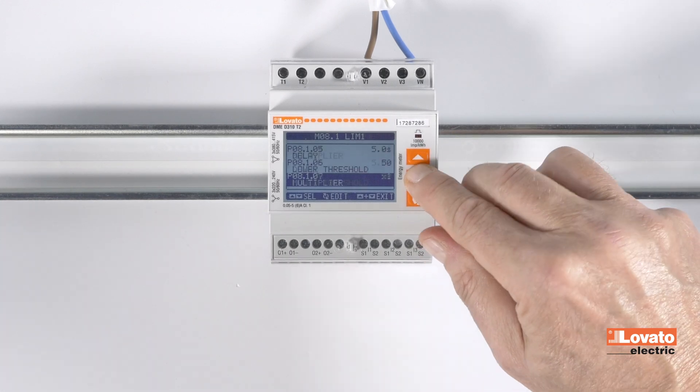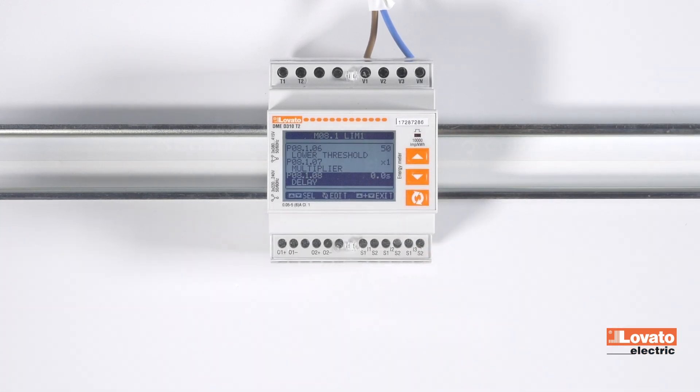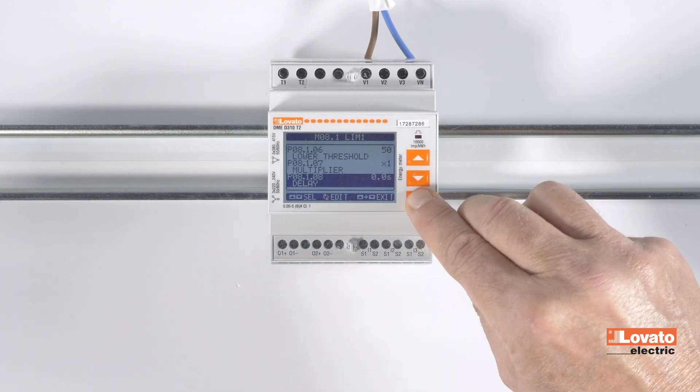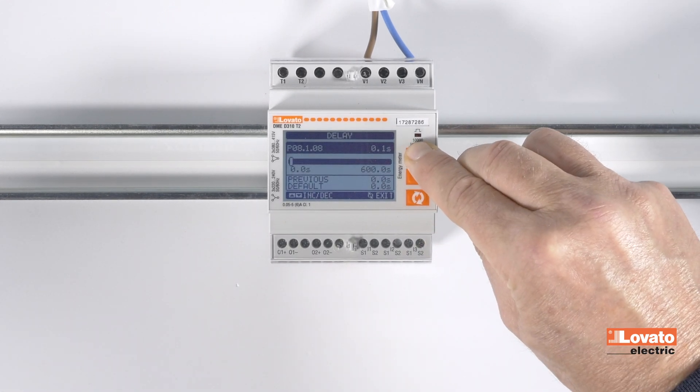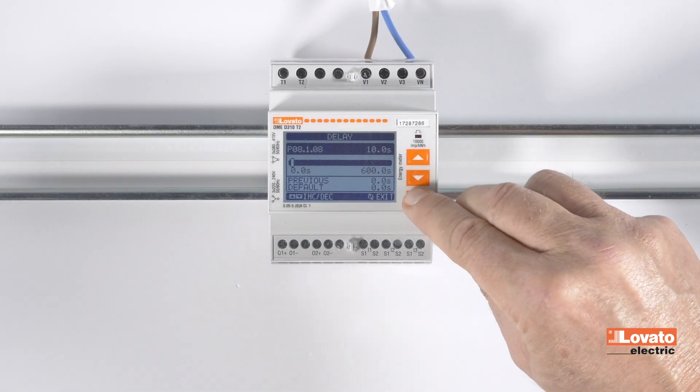Here again we need to set the delay time for this variable. Enter the item on the menu and set the time at the value established. In our case, 10 seconds.